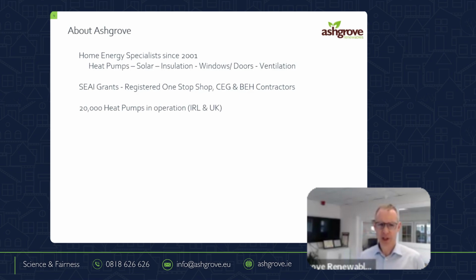We have about 20,000 heat pumps in the marketplace around Ireland and the UK. I would say any of our large ones, the ones we'll see in a second here, the 2 megawatt ones, are typically in the UK. But we have a huge number of heat pumps in operation. We know very definitely what works and what doesn't work. And so we're not here trying to sell Mitsubishi heat pump over a Panasonic or a Daikin or whatever. That's not what today is about. It's about principles of operation, and the rules should apply to pretty much any heat pump.